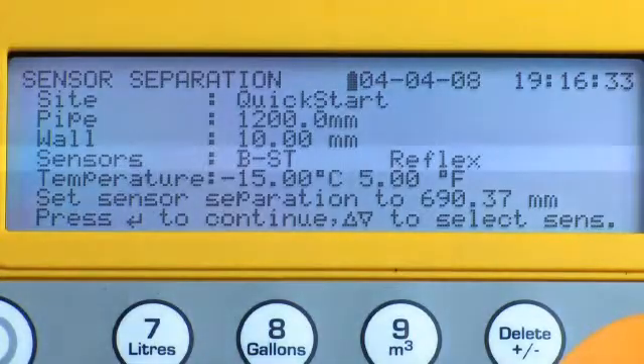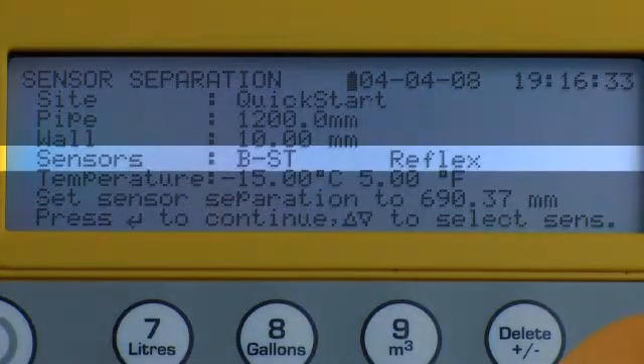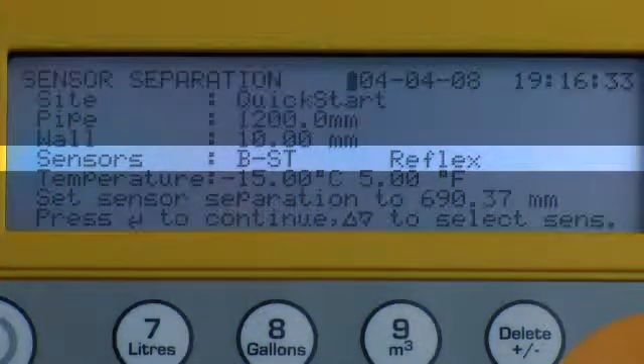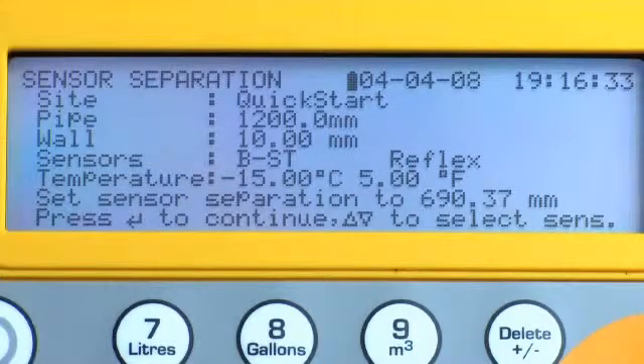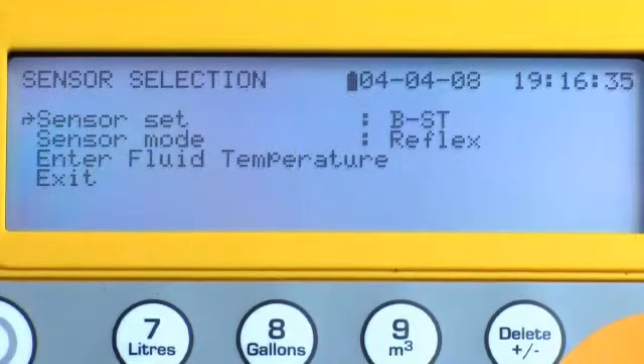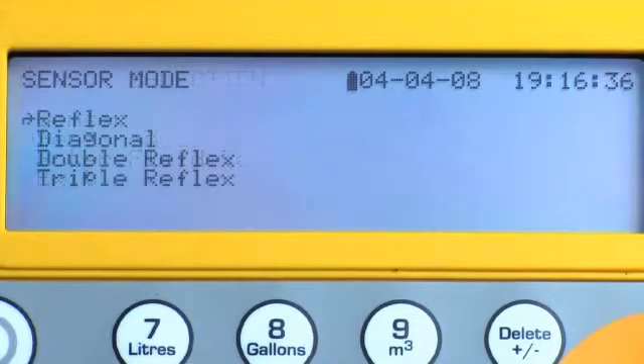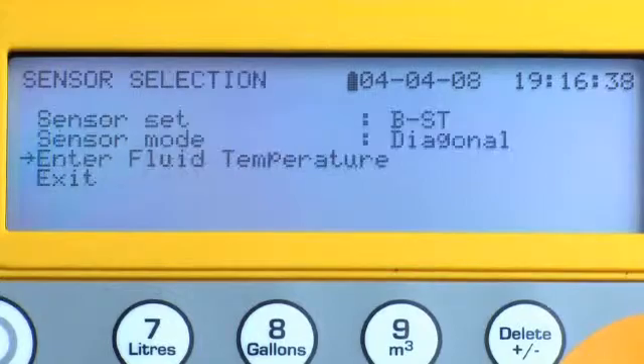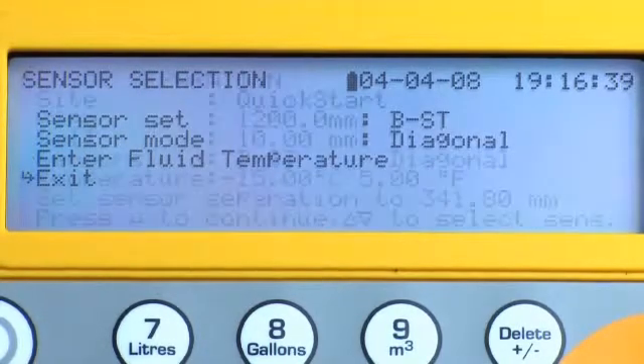The mode of operation just demonstrated is called reflex mode. On large pipes and potentially difficult applications, we may need to set up the sensors in diagonal mode to improve signal levels. For diagonal mode operation, press scroll and select sensor mode. Press enter and select diagonal mode. Scroll down to exit and press enter.